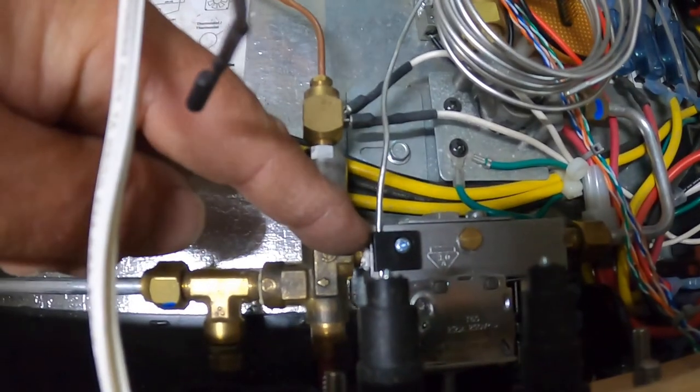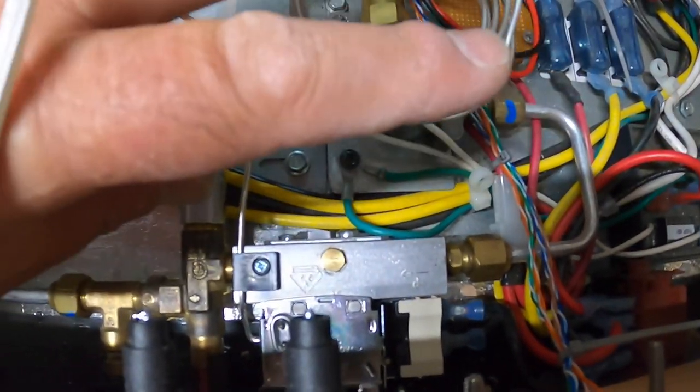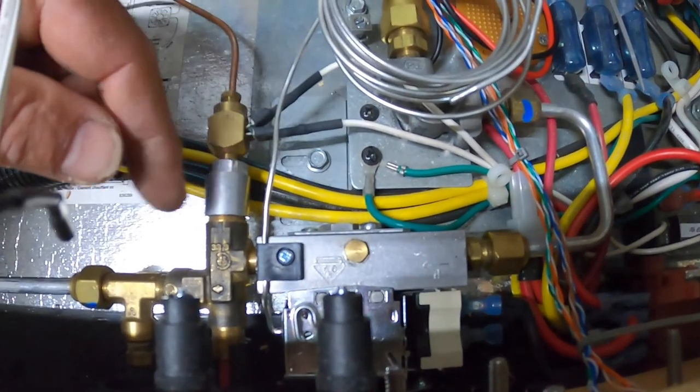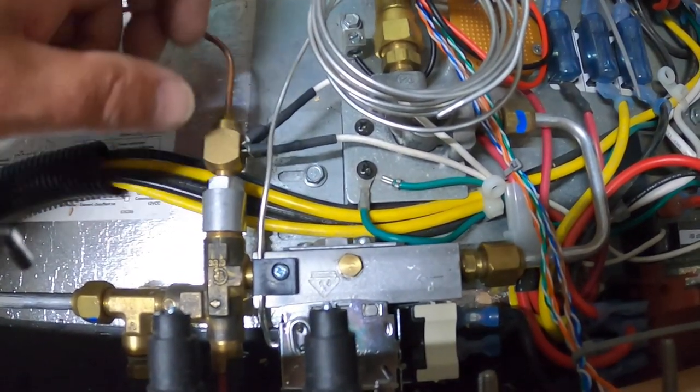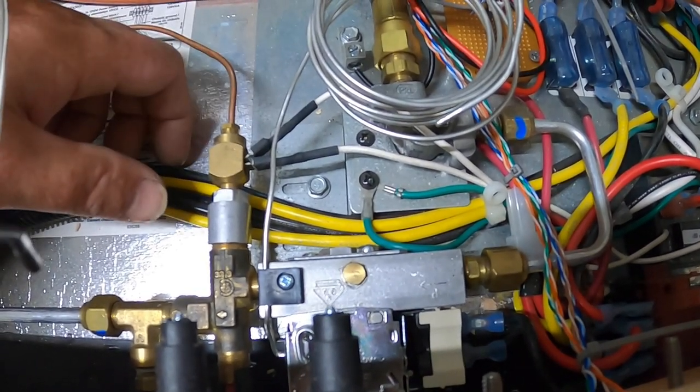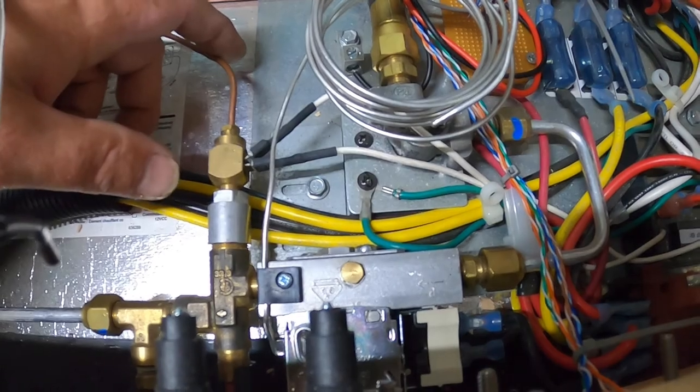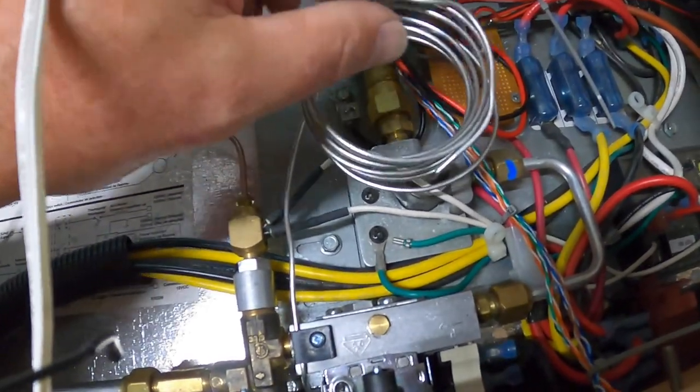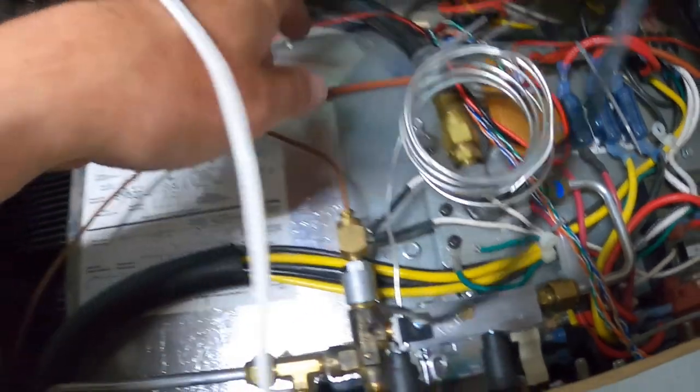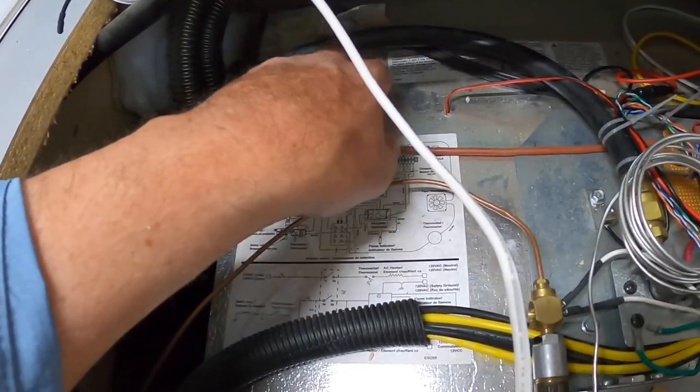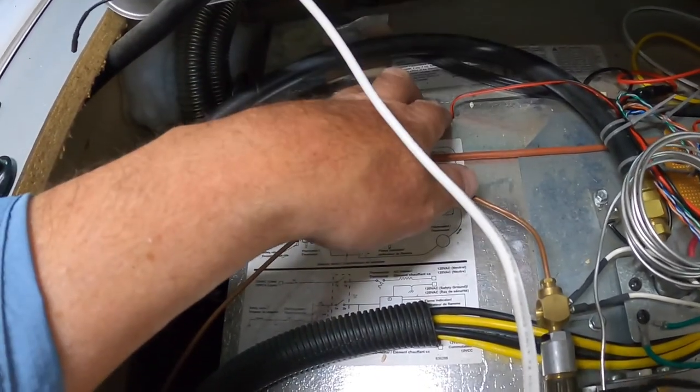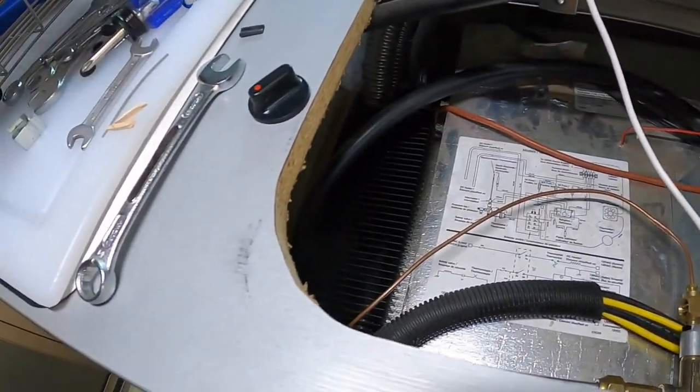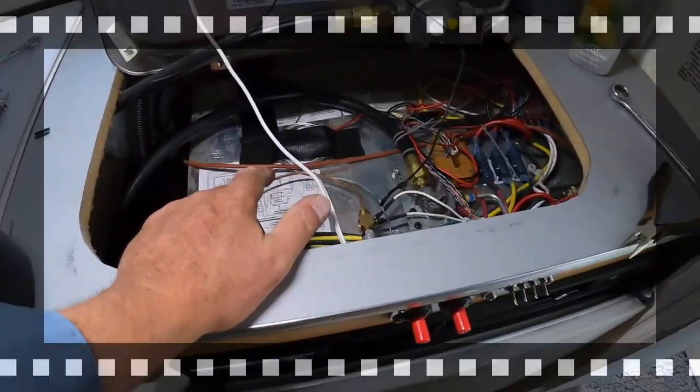here, here, and here. All four of the connections that I loosened, I'm going to put some soap on. I might put some soap around the other guys, too, and watch for bubbles. That's a great way to tell if you've got a leak or not. And remember, you don't want any gas leaks. So now we're going to go ahead and run this sensor back in the hole back there. Leave the excess coiled right in the, in this direction. Put some new tape down on it to hold it. These clips back in the fridge. So let's get at it.